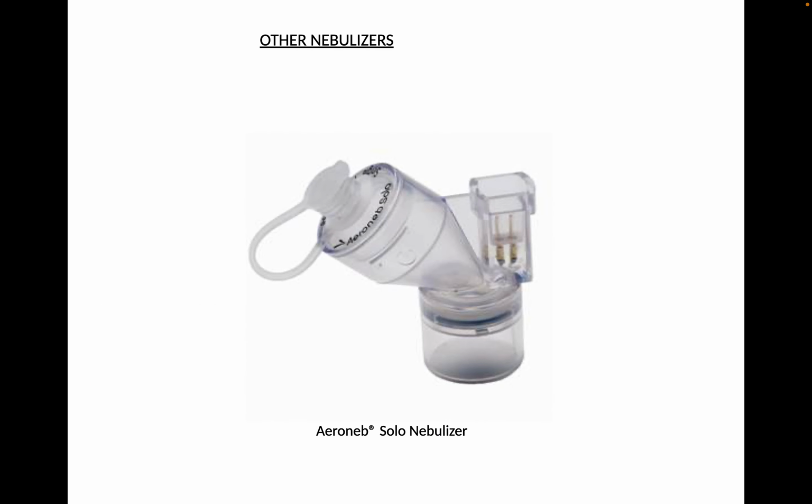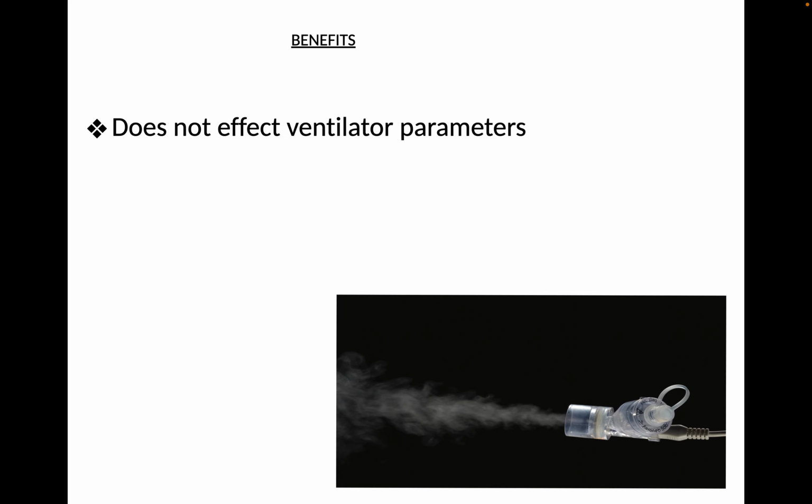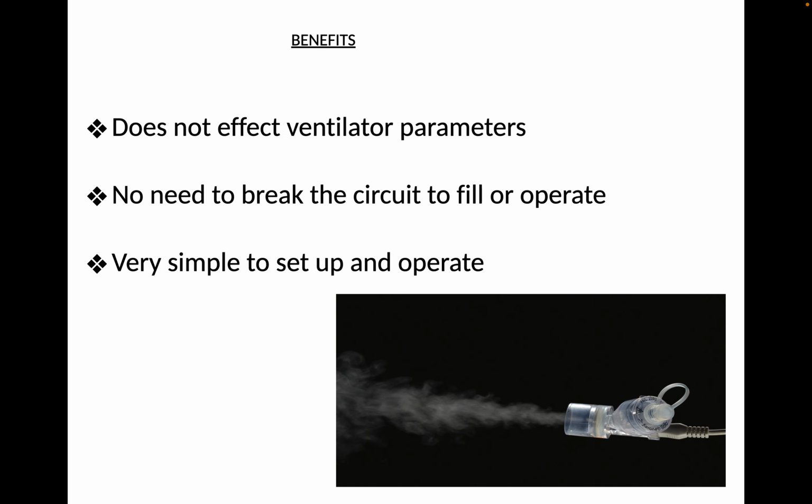The other nebulizer is the Aeroneb Solo, which can also be attached to the ventilator after the Y-piece. The benefits are that it does not affect the ventilatory parameters, and there is no need to break the circuit. It is very simple to use.